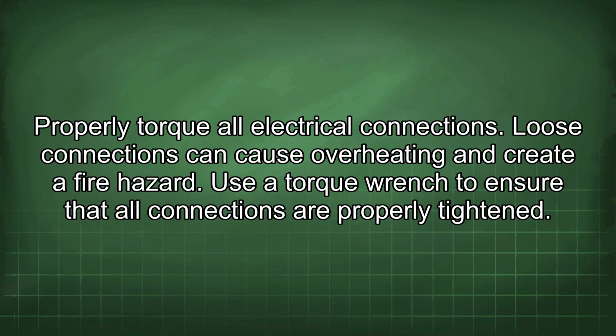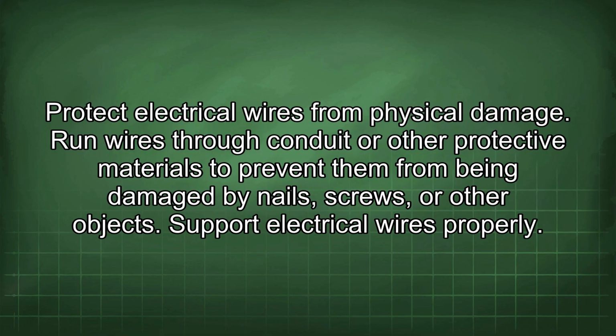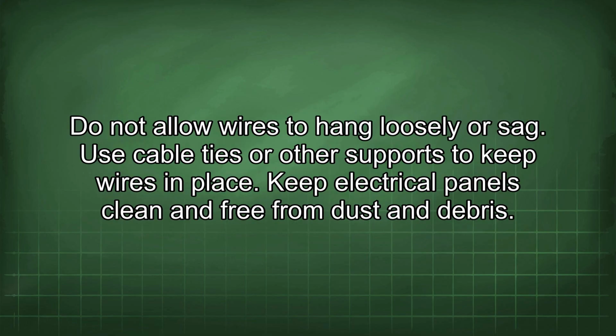Properly torque all electrical connections. Loose connections can cause overheating and create a fire hazard. Use a torque wrench to ensure that all connections are properly tightened. Protect electrical wires from physical damage. Run wires through conduit or other protective materials to prevent them from being damaged by nails, screws, or other objects. Support electrical wires properly. Do not allow wires to hang loosely or sag. Use cable ties or other supports to keep wires in place.